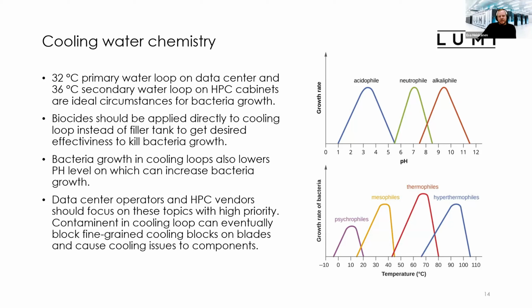And as you can see from this graph, pH 8 would be pretty much optimal to have in the cooling loop. So this is something that data center operators and HPC vendors should focus on with high priority, because this kind of contamination in the cooling loop can eventually block these fine-grained cooling blocks on the plates, and this can cause cooling issues to the components.